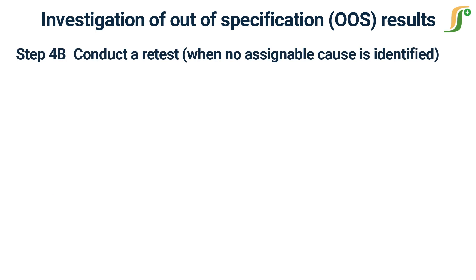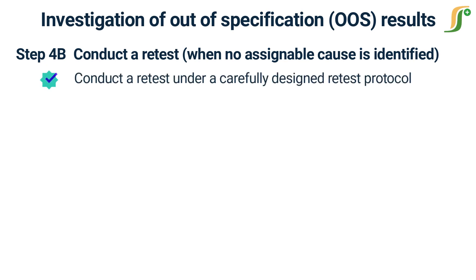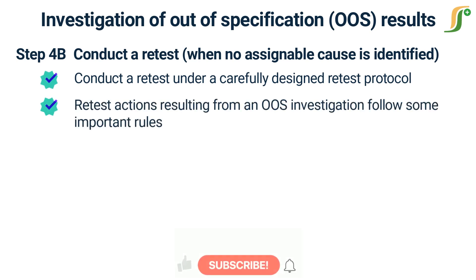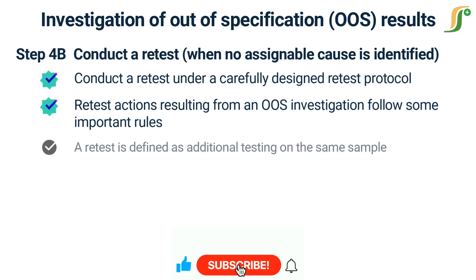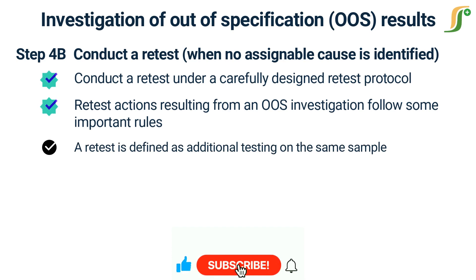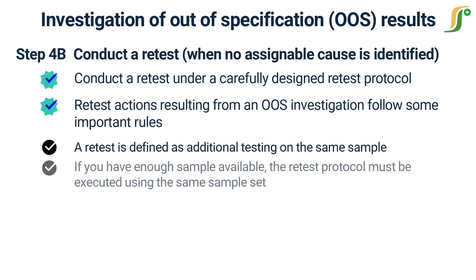Step 4b: Conduct a retest when no assignable cause is identified. You should conduct a retest under a carefully designed retest protocol based on the specific problem identified. The history of the product, method, and batch must delineate the number of retests to be performed. A retest is defined as additional testing on the same sample, from the same bottle of tablets or capsules in the same drum or mixer. Retesting is acceptable only after the investigation has commenced and only if retesting is appropriate to investigate the OOS event. If you have enough sample available, the retest protocol must be executed using the same sample set that was the source of the original out-of-specification result.